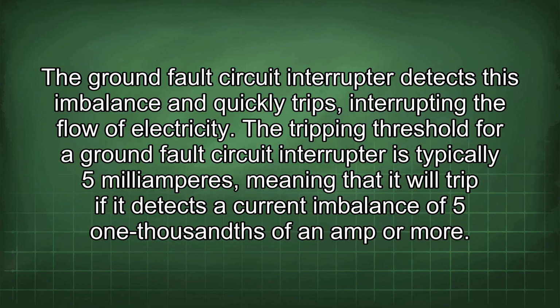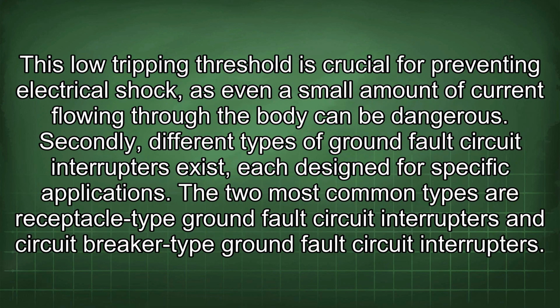The tripping threshold for a ground fault circuit interrupter is typically 5 mA, meaning that it will trip if it detects a current imbalance of 5/1000ths of an amp or more. This low tripping threshold is crucial for preventing electrical shock, as even a small amount of current flowing through the body can be dangerous. Secondly, different types of ground fault circuit interrupters exist, each designed for specific applications.